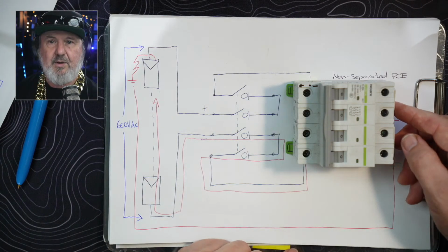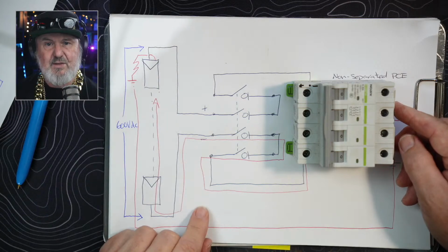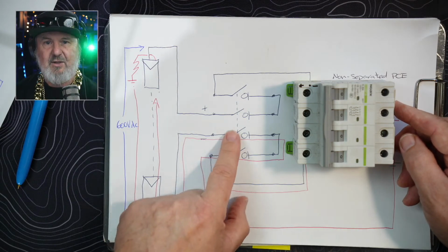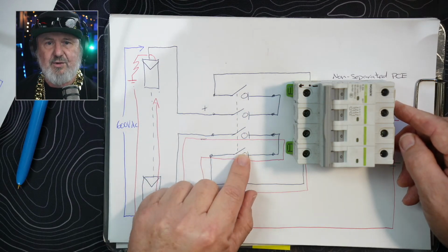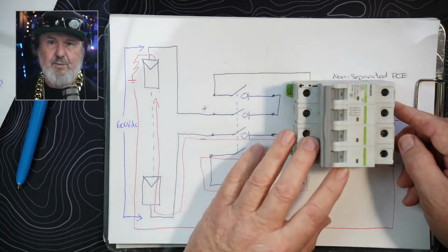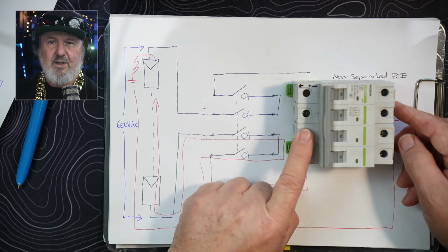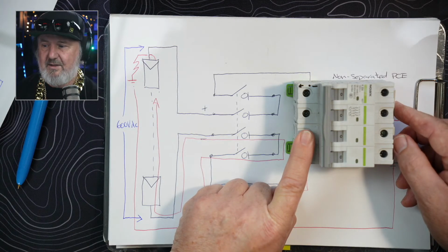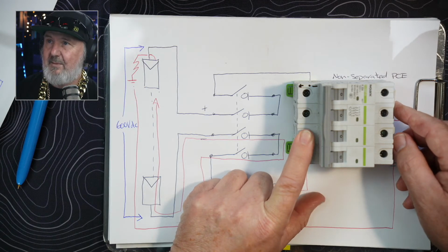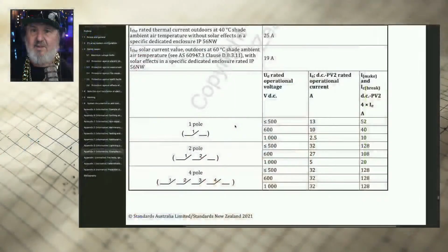So I've got 4 poles, but remember, with a transformerless inverter, it's not going to go through 4 poles, only going to go through 2 in series. So even though it's a 4-pole device, I need to know what its 2-pole in series rating is. So that's where we come back to this table here for this imaginary DC isolator. And it's showing us ratings for 1 pole, 2 poles in series, and 4 poles in series.